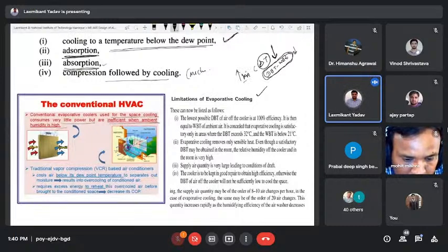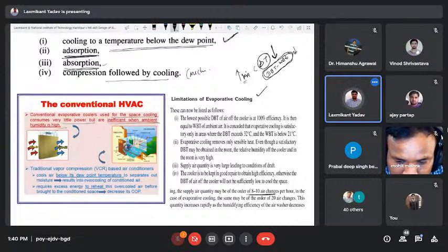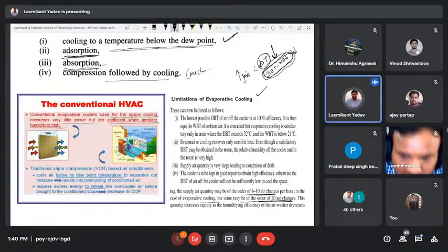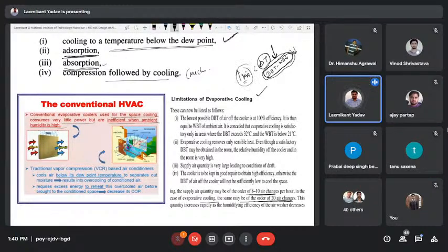You observe in summer that every home has a cooler, and the mass flow rate is very high. In a vapor compression air conditioning system the air changes are 8 to 10 per hour. However, in evaporative cooling the same may be of the order of 20 air changes per hour, because delta T is less. The sensible cooling we achieve with an evaporative cooler is less, so we require a higher mass flow rate. The supply air quantity is very large, leading to a condition of draft. We do not feel comfortable because the velocity is higher in an evaporative cooler.